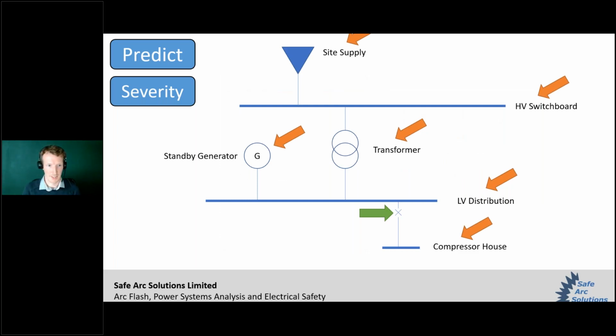There's a number of inputs to an arc flash study, and realistically gathering the data and building up the system model is usually the thing that takes the most amount of time. It can be a real time sink depending on how well documented the site is and how readily accessible information is. Even for the simple system that's shown on the screen now, you can be looking at quite a lot of data gathering for things like the site supply, transformers, generators, the switchgear themselves and cables. A crucial piece of information is your overcurrent protection settings for relays or the ratings of your fuses. This is one of the big drivers of arc flash incident energy. That might be in a schedule somewhere, but equally it might be something that's out of date, so you need to go out and do a full survey of equipment on your site.